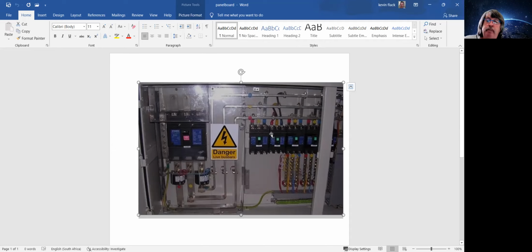And this is where the type testing is such an issue when it comes to having circuit breaker panels pre-tested. One, they are checked for short circuit viability. They are checked for compartmentalizing. They are actively tested before you have a short in your warehouse or your factory, before there's an issue.